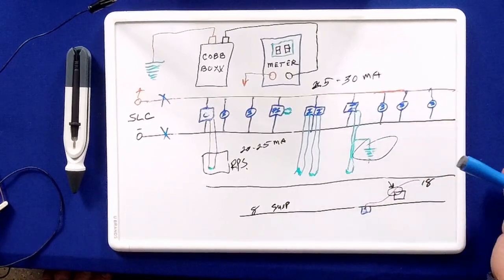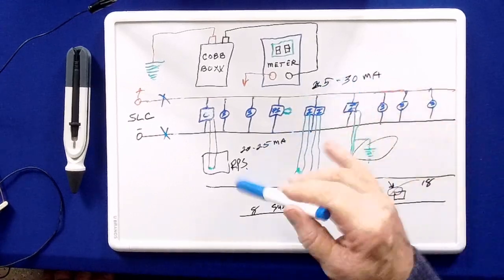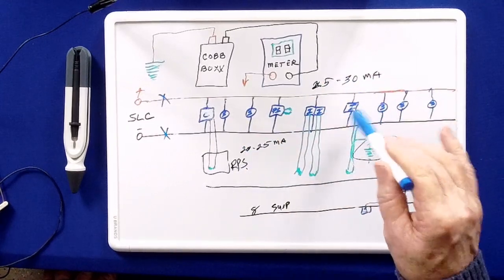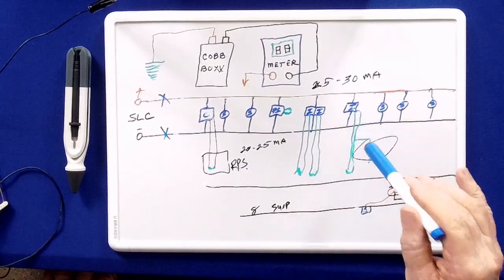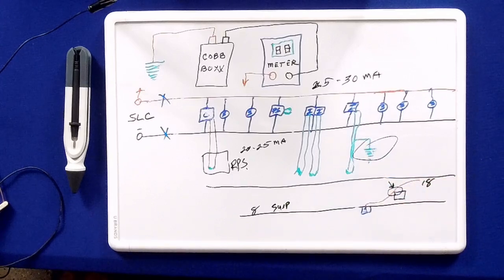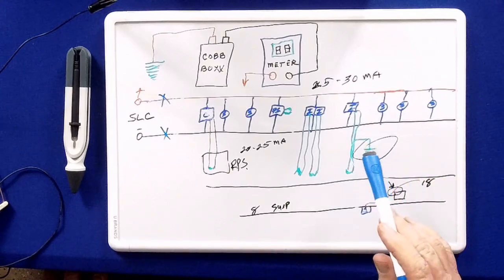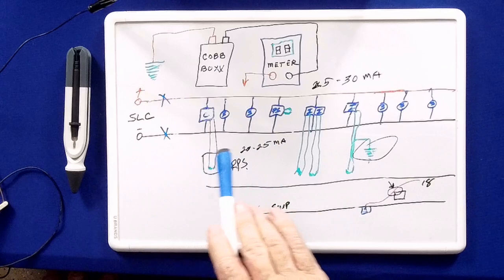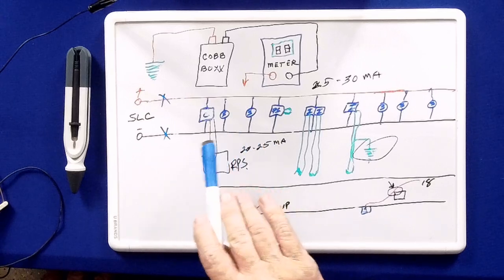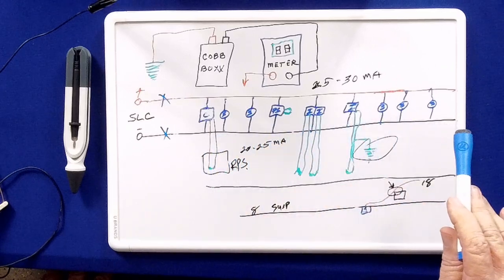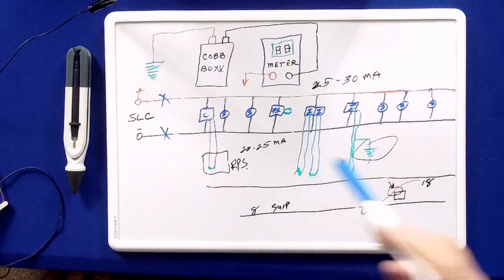on this initiating module. So this is the reading you're going to see when it's an initiating module in the field that's grounded. Now, what this does for you is it allows you to eliminate a lot of times anywhere from 80 to 90% of your circuit. You know it's going to be on a module.